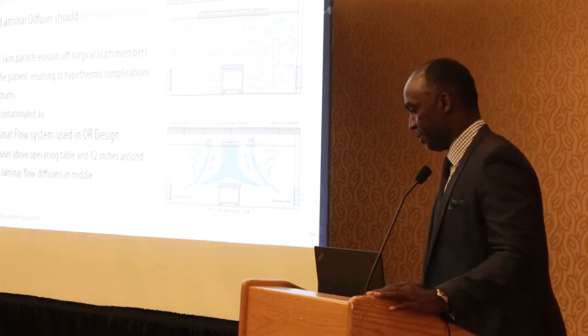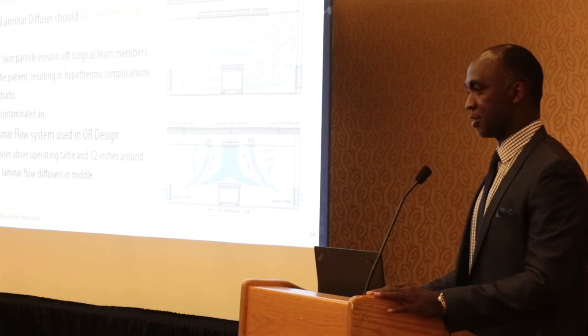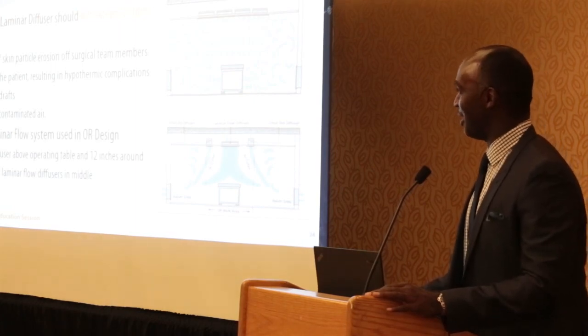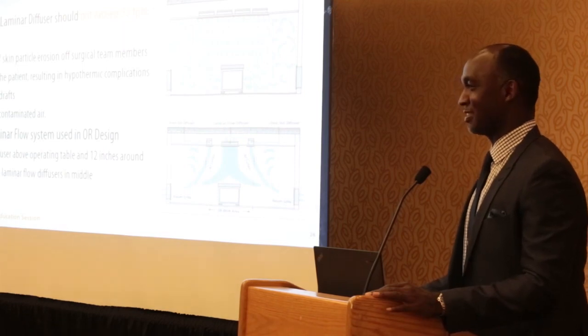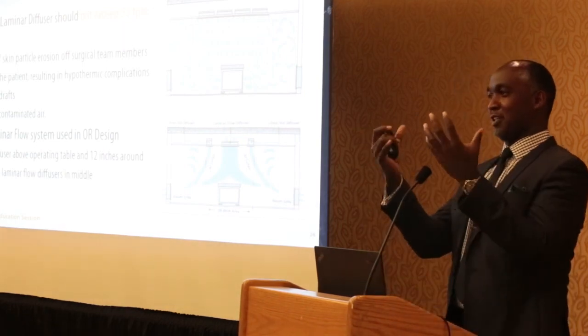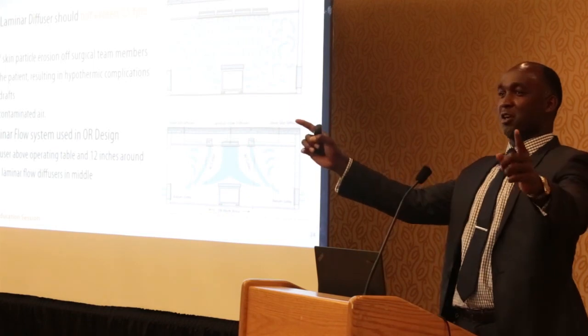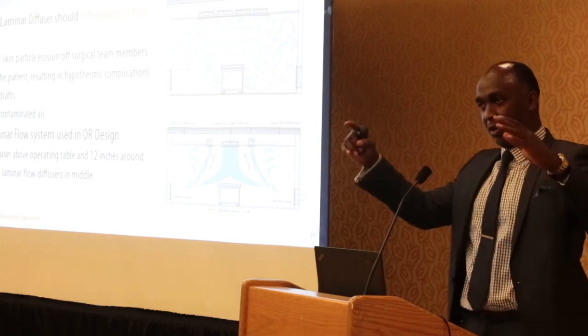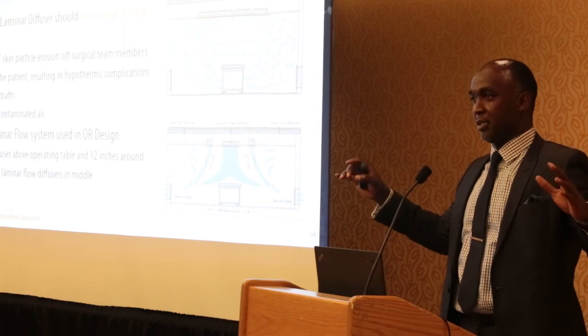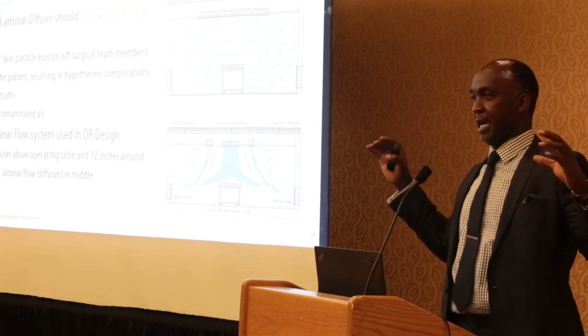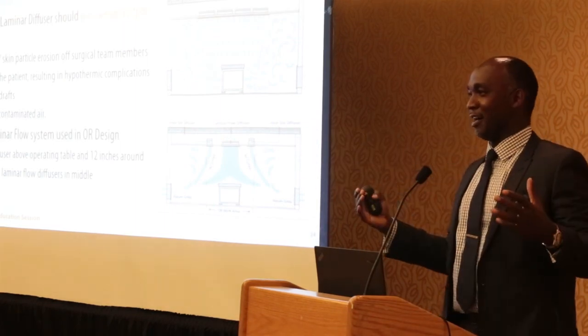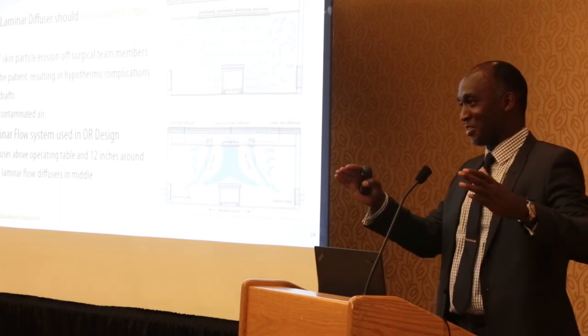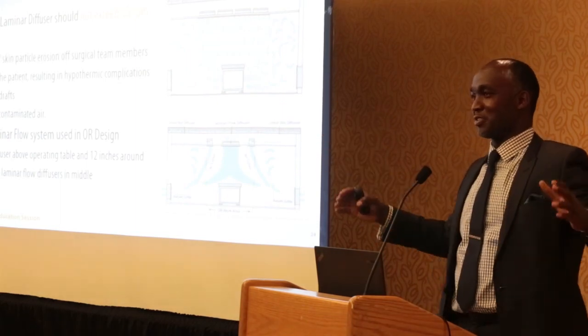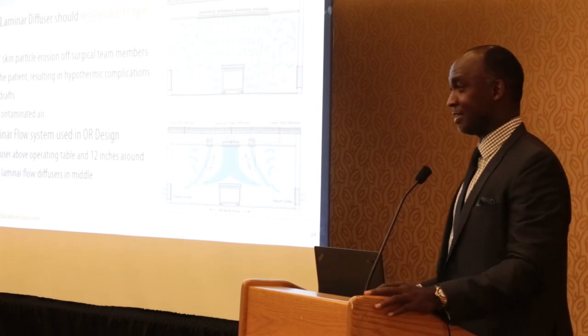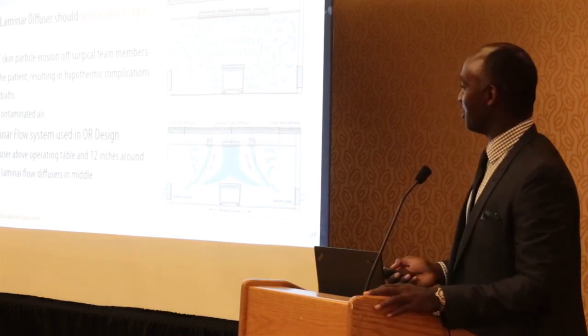There are two types of laminar flow system used in ORs. There's the full laminar system, or the cheaper system, in which you have air curtains, meaning that you have the laminar flow in the middle, and around the edges you have slot diffusers at higher velocity. That's not laminar, it's just higher velocity, and the thought is that it creates a barrier, and your laminar flow is insulated from the external environment. It doesn't work as well for hybrid ORs.